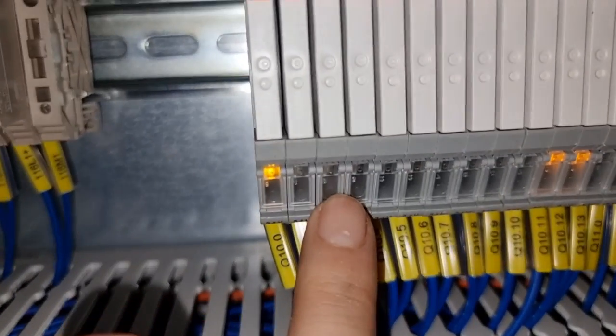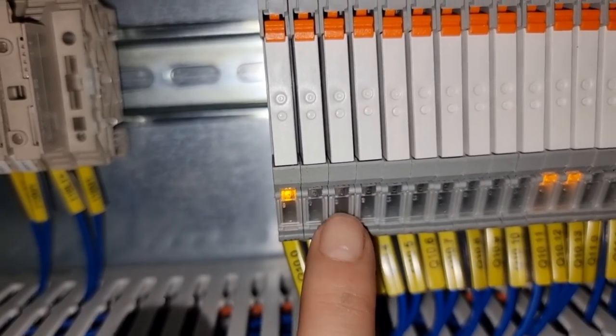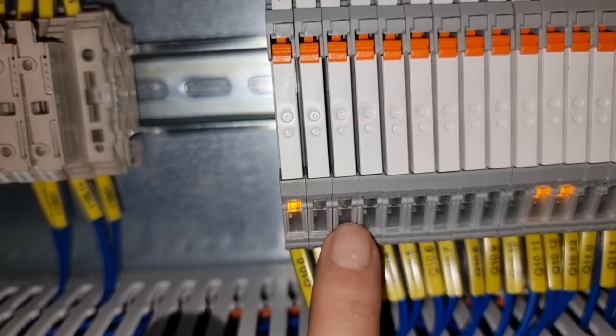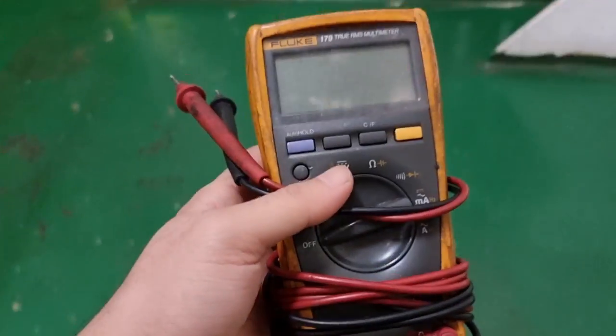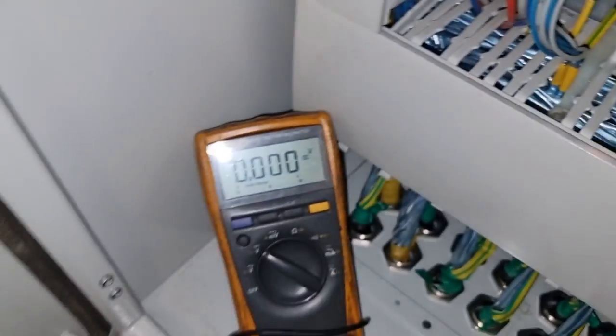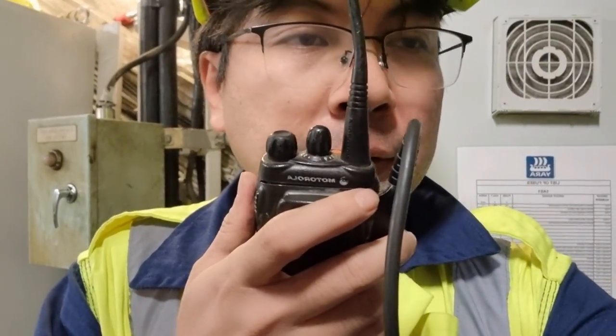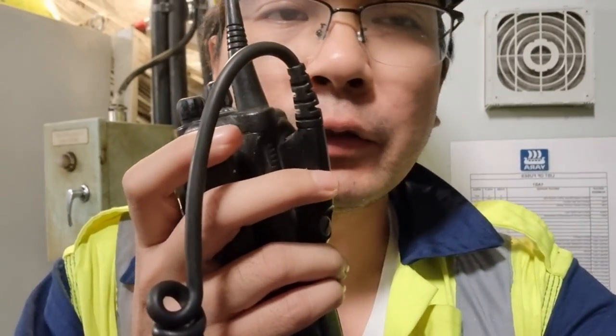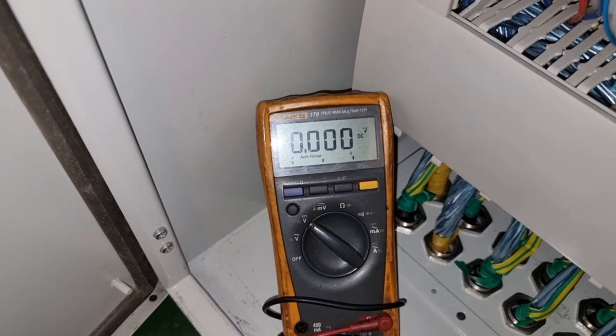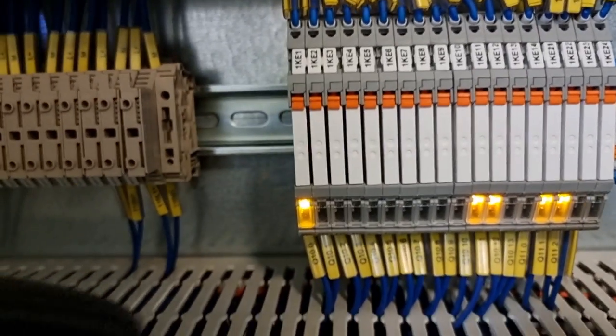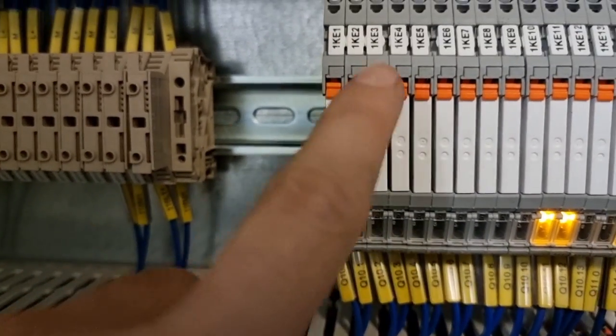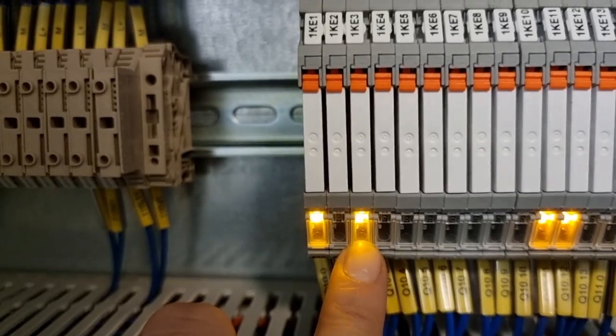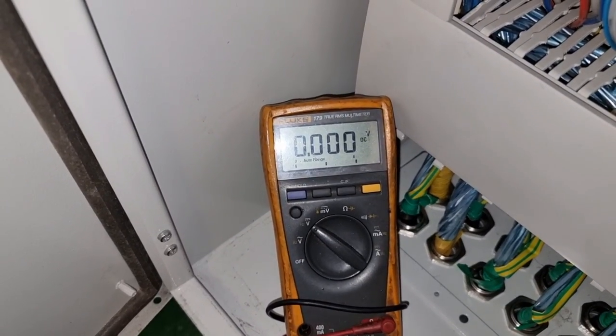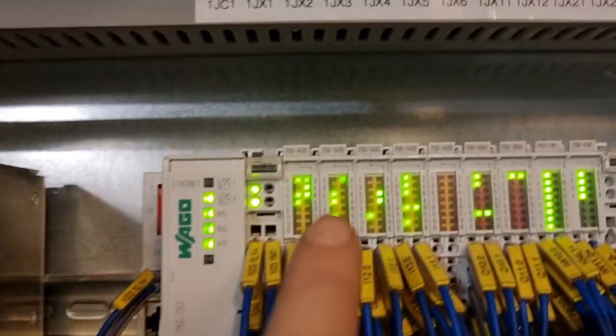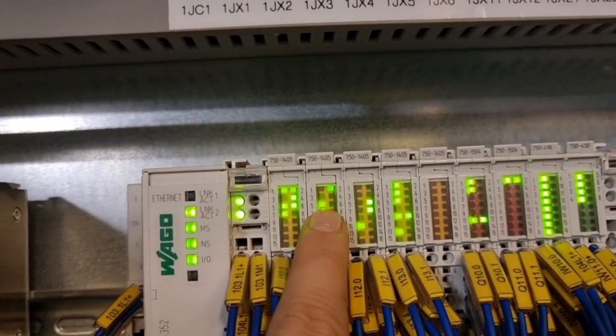And now we are going to test our system and see if this one will give an indication that it actually supplies 24 volts to our valve. So I connected our multimeter across these terminals so that we can also measure if we are having 24 volts once we give an open command on our control panel. So the second engineer is in the control panel, and as you can see, there is an indication on our relay block and it's now giving 24 volts.